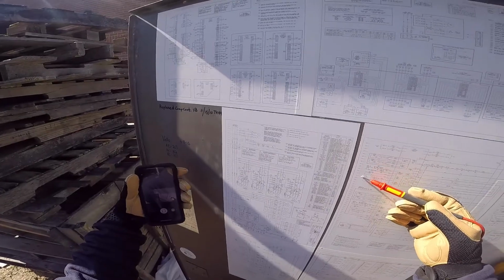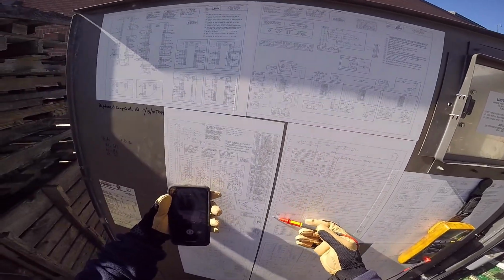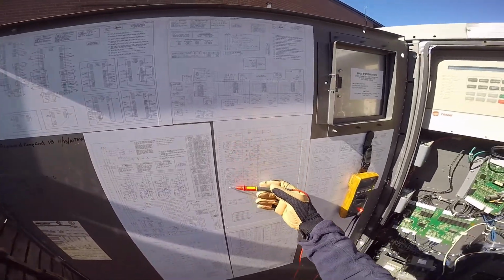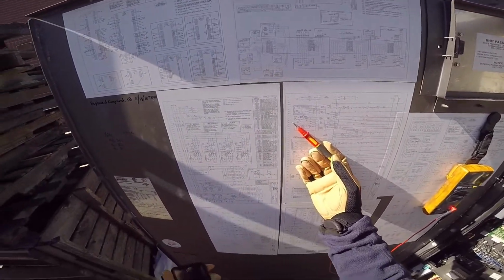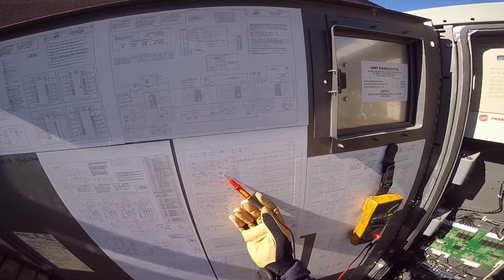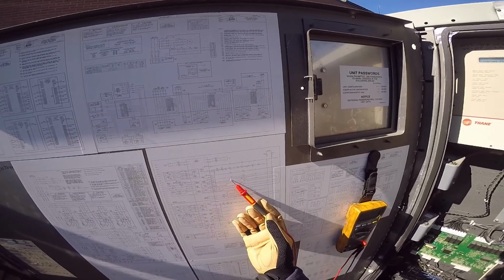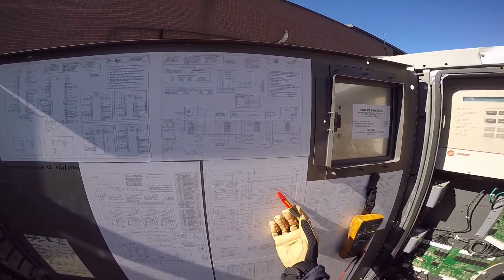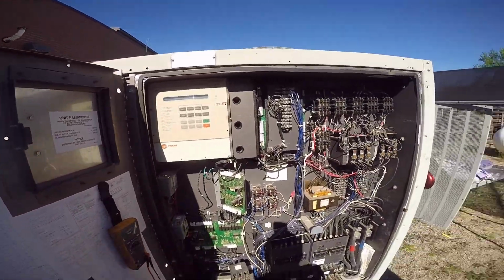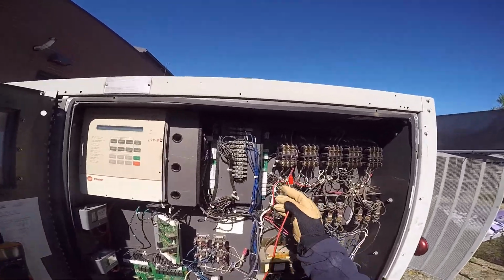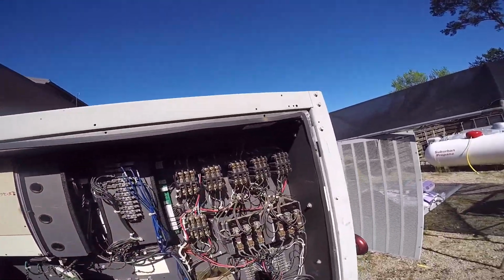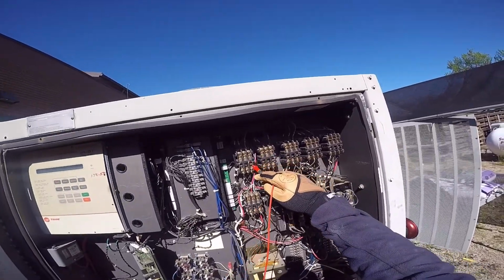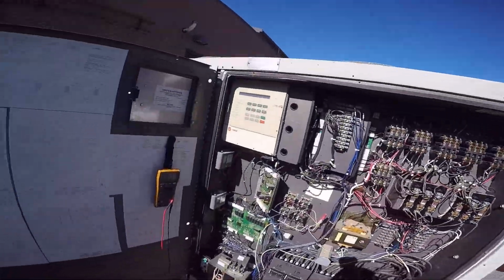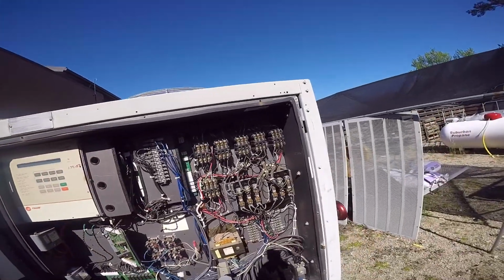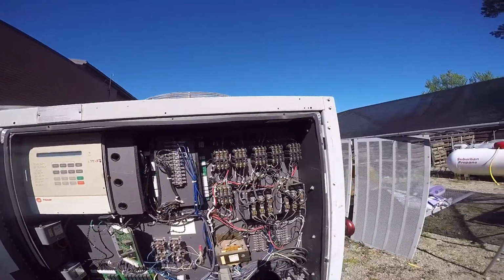your line numbers run down the left side of a ladder. Okay, so I find 130, and then I just follow 130 until I find a 1K7, and then I find my 1K7. It gives me a wire number, and I can then find the wire number on the bottom of the contactor. I know that's 1K7. I don't want to look that up no more, so I write it down: 1K7, 1K8, 1K9. The biggest thing with air-cooled chillers is condenser fan motors going out. So we definitely want to check these.